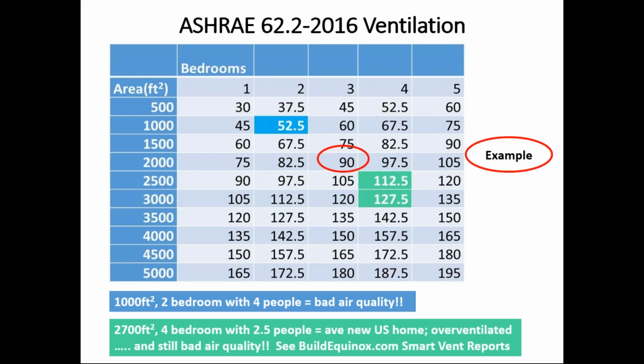Current ventilation standards. This is a table taken from ASHRAE 62.2, the residential ventilation schedule from the ASHRAE Society, and their 2016 version. It's updated every 3 years, typically. And the problem with ASHRAE ventilation, ventilation's essential, and it's good that there's at least this ventilation schedule, but it does not reflect a healthy home or how to maintain a home in a healthy condition. It does not specify the importance of distribution of that air within the home. So there's a lot more beyond this that's needed.